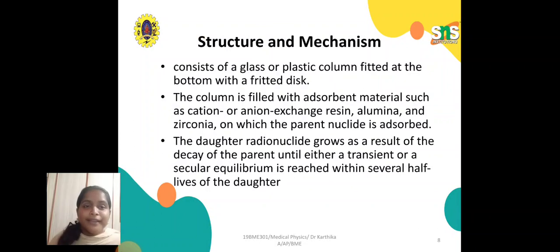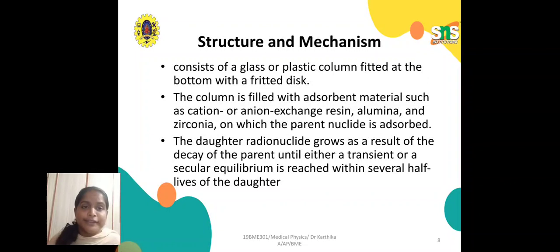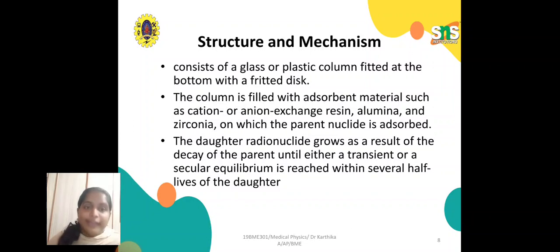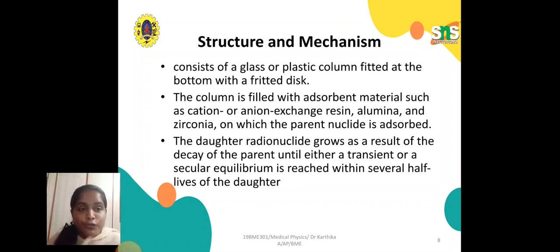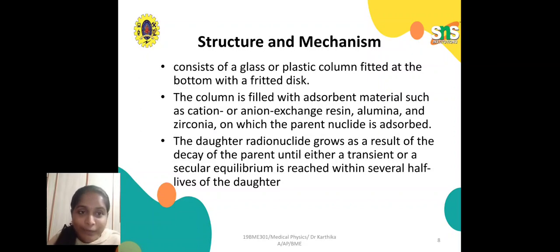The structure and mechanism of the radionuclide generator consists of a glass or plastic column fitted at the bottom with a fritted disc. The column is filled with an adsorbent material such as cation/anion exchange resin, alumina, or zirconia, on which the parent nuclide is adsorbed. The daughter radionuclide grows as a result of the decay of the parent nuclide until either a transient or secular equilibrium is reached within several half-lives of the daughter.